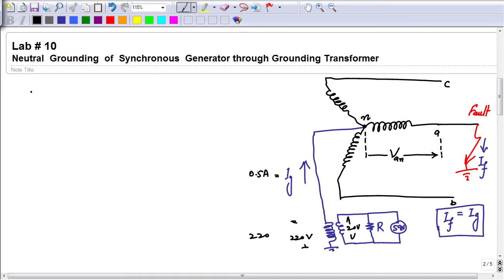So that is the fault voltage. We can write it as VF. In case of line to ground fault it will be 220. In this particular condition, the rating of the primary of this transformer and the fault voltage are both the same. It could be different, because the rating of this grounding transformer primary side should be either equal or greater than that. If it is greater, then definitely VF and the rating of this transformer primary voltage will be different. So this is the VF.